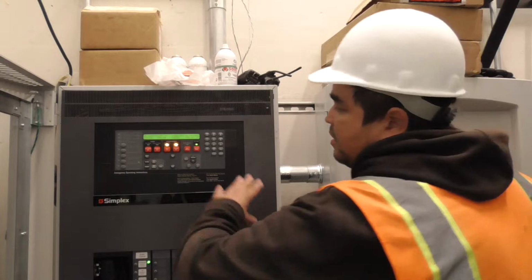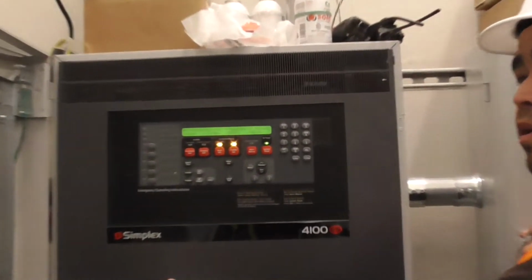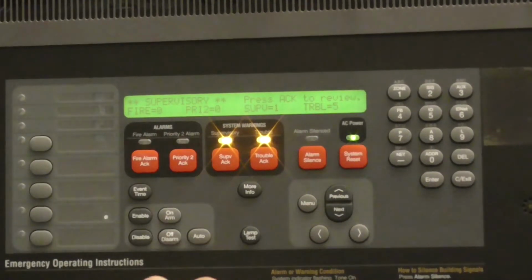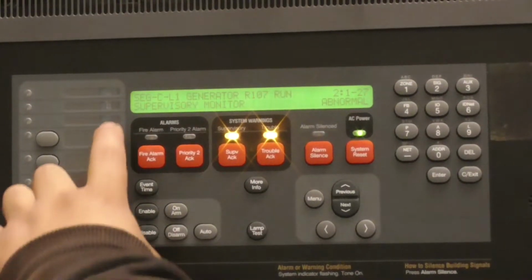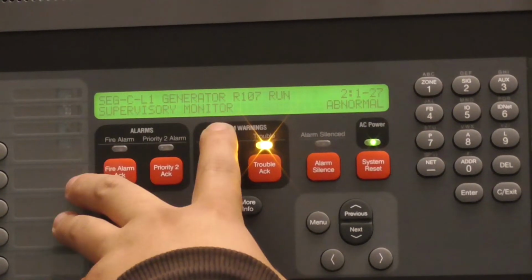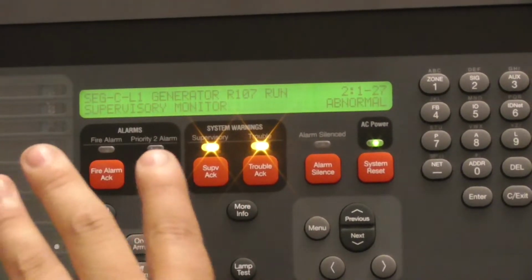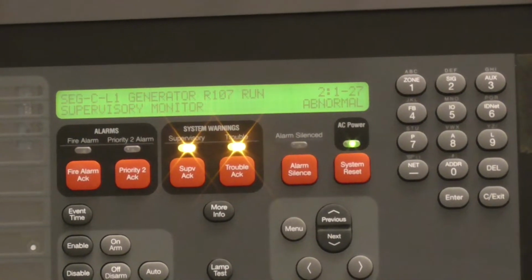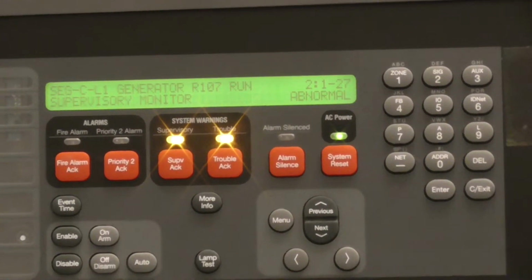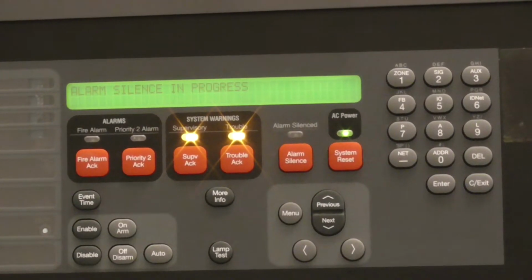Yeah, I mean, so let's just say, for instance, one of the bedrooms on the 6th floor goes into alarm, right? General alarm? Into the local alarm. Oh, local, okay. Local alarm, right, for the supervisory. Supervisory will flash. Okay. You acknowledge the supervisory. It'll tell you where it's at, the description of the location, the room. And once you acknowledge it, it's going to continue to keep playing the code 3 inside the unit. It won't silence it inside the unit, though? No. Okay. And then until somebody comes and presses alarm silence, it'll just silence it, right?